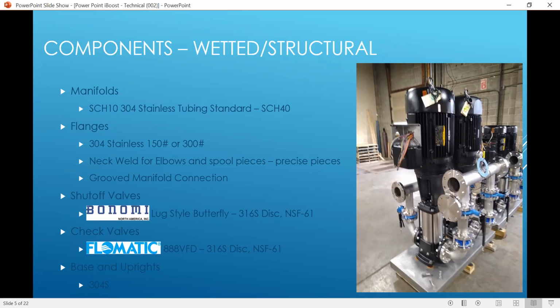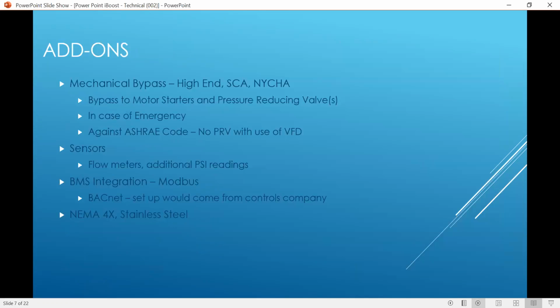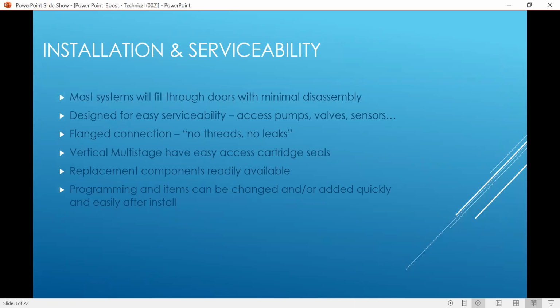If the customer wants to save cost, then we usually will line them up with an end suction unit. But the end suction pumps have their limitations. Sometimes they're more reliable because they can carry more volume and there are not as many moving parts. But they're also limited on their head pressure. So if you're looking at something over 190 feet of head, we recommend switching up to the vertical multi-stage.